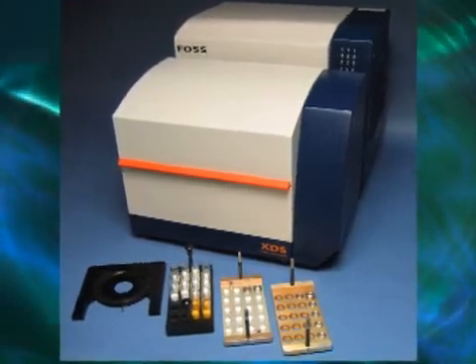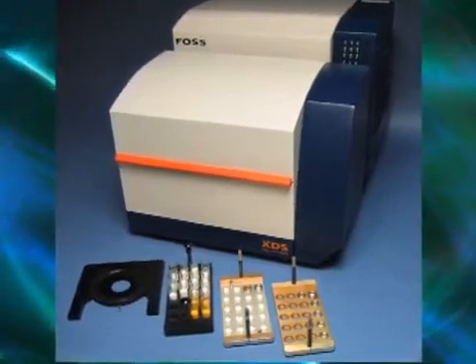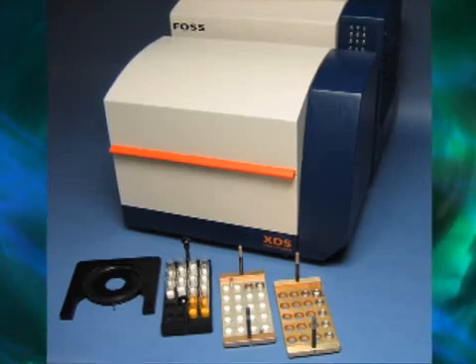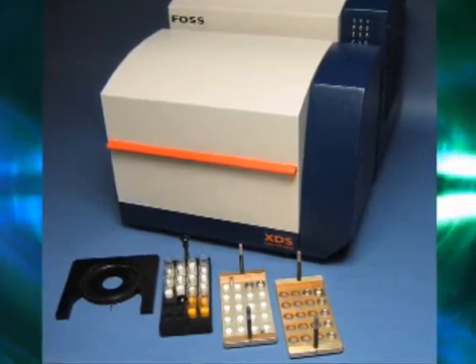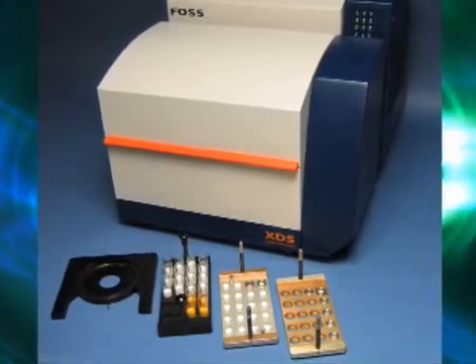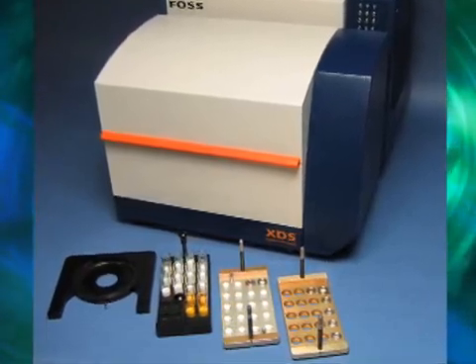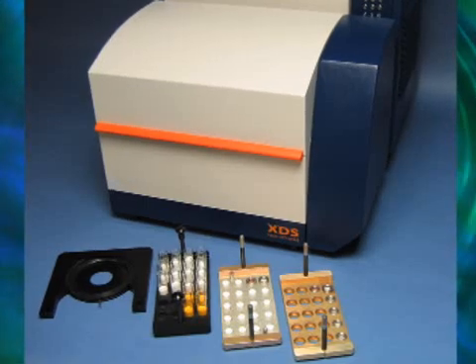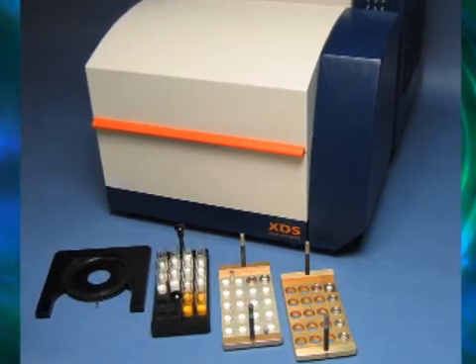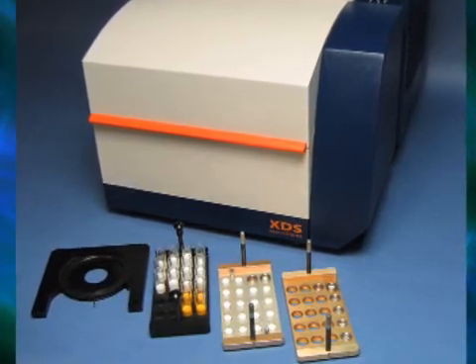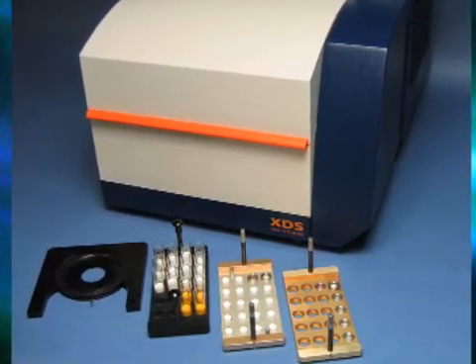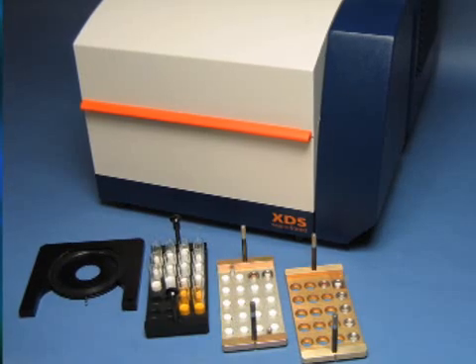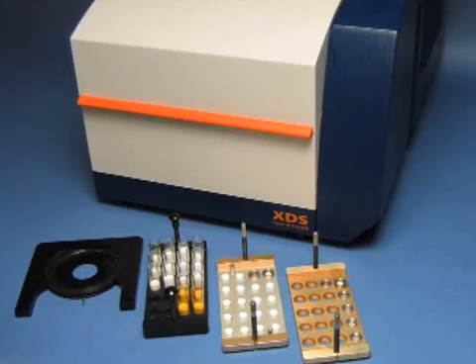The FOSS XDS Master Lab is a near-infrared analyzer that provides rapid, precise, and non-destructive chemical analysis down to the microgram level in the laboratory and during the manufacturing process.